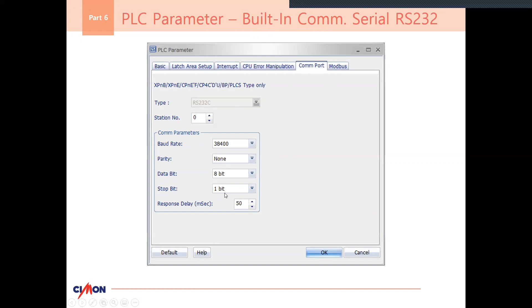Here's our COM port parameter setup. So you declare the station number, the type of communication, RS-232, 485, 422. This is for serial communication COM port. And then the baud rate, making sure that all of these match specifically to what the device you're talking to has, in terms of baud rate, parity and all that fun stuff. And then this is where we do our Modbus slave setting.